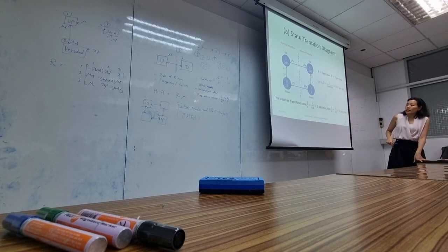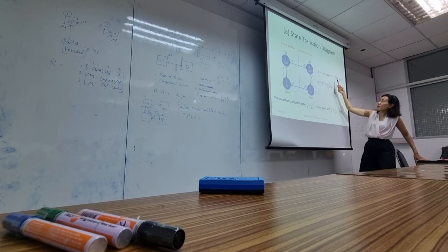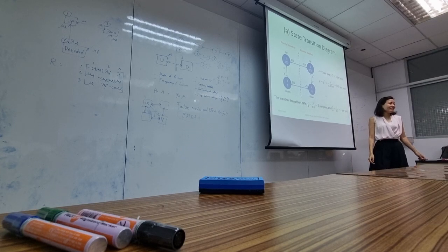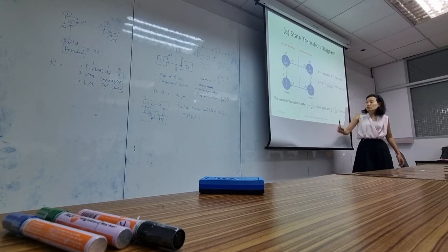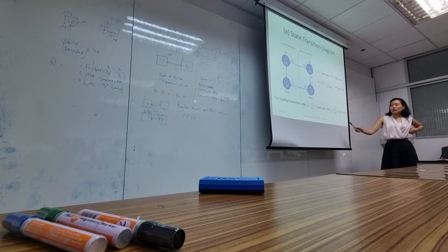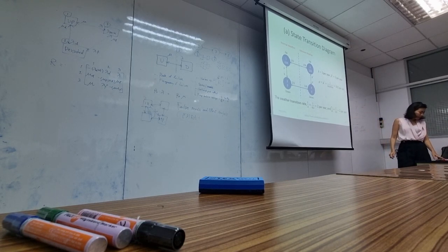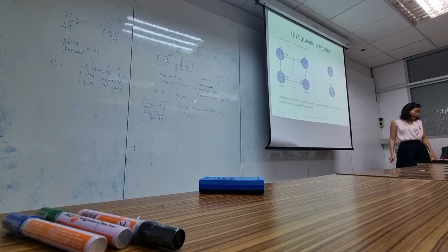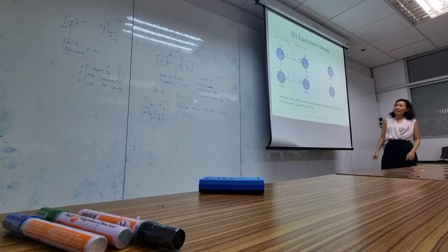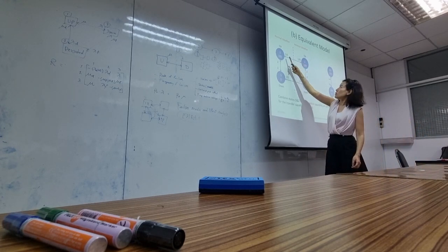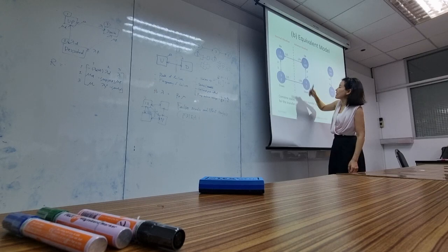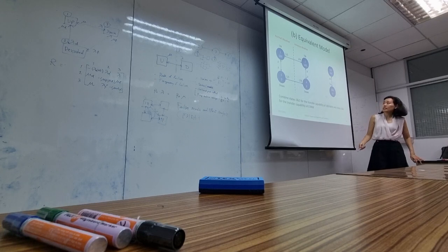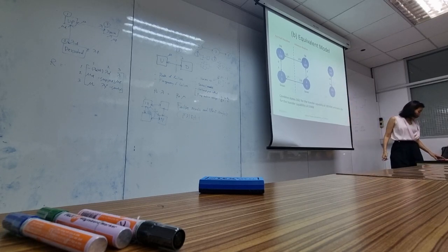Okay. The weather transition rate. If you have the transition rate here as per year, the weather should also be in per year. So it's 2 per year, and in that case, it's also 2 per year as well, because its duration is 0.5, right? Equivalent model happens when we combine the states 1 and 2, which have the same 100 capacity, and we combine 3 and 4, which have 0 capacity, so that we can have this equivalent model.